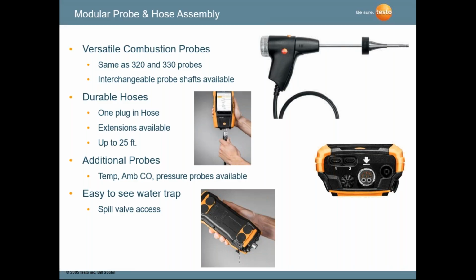Water trap is integral to the instrument. You'll see in that bottom photo, someone's using a spill valve to get access to get the water out of the instrument. On the top where the probe handle is, there's an acrylic cover there. That is where your particulate filter is. It captures the particulates in your flue gases. So you're using this probe and hose assembly, very interchangeable, very modular on your unit. It can be used on residential applications, and with the extension hoses and extension probes, you can use it on industrial applications as well.